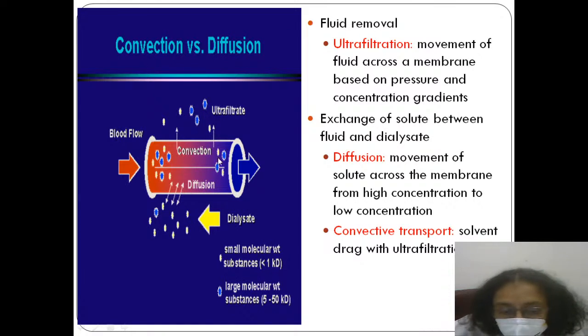The fluid has to move from the blood to this dialysate, and for that a transcapillary pressure, or a transsurface pressure across the surface, is applied, and that pressure will push the fluid out into this dialysate fluid. The other thing that happens is there is a difference in the concentration gradient, or the osmolality, between this fluid and this. If the osmolality over here is higher, the concentration is higher, then that will draw in fluid, while if the concentration outside this capillary is higher, it will draw the fluid from the blood. So the concentration gradient and the transcapillary pressure applied will push fluid out, will filter fluid out. The solute exchange is slightly different.